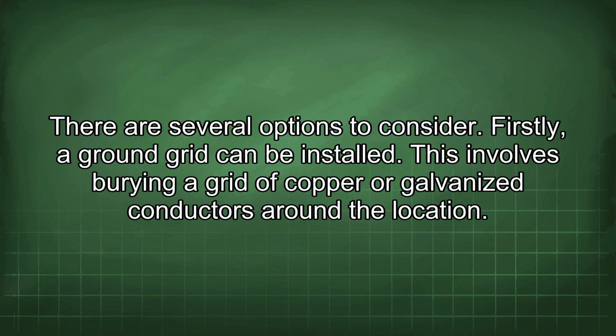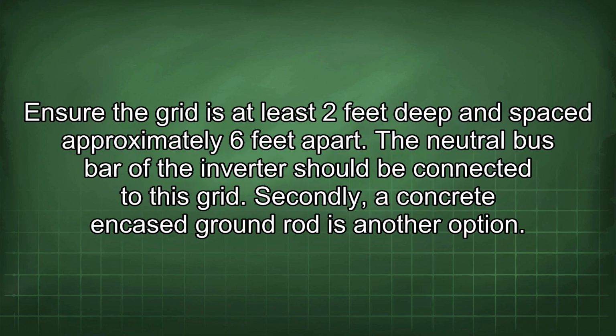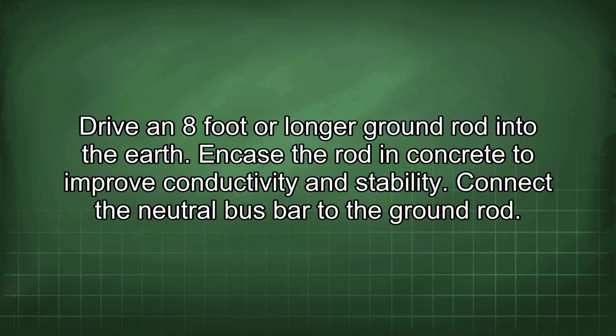This involves burying a grid of copper or galvanized conductors around the location. Ensure the grid is at least 2 feet deep and spaced approximately 6 feet apart. The neutral bus bar of the inverter should be connected to this grid. Secondly, a concrete encased ground rod is another option. Drive an 8-foot or longer ground rod into the earth. Encase the rod in concrete to improve conductivity and stability. Connect the neutral bus bar to the ground rod.